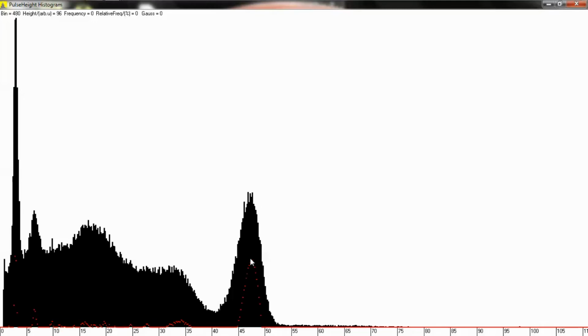But 662 is where most people tend to put it. And that's probably this big guy right here. In fact, I know for a fact it's this big guy. But if you didn't know anything about this, if you were just looking at it for the first time, you could probably deduce that since there's nothing over here, and you know that 662 is the highest peak that cesium-137 puts off, and this is a very pronounced photo peak, we can imagine that this is 662, and it is. So let's put our mouse right here, and we're going to hit B for begin, and then we're going to put our mouse over here where it ends, and we're going to hit E for end. And then we've highlighted this whole area as a region of interest.